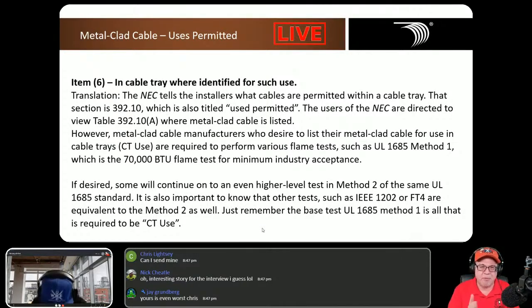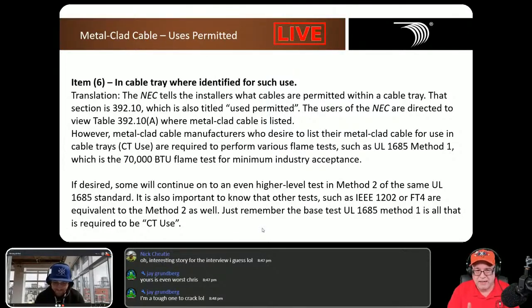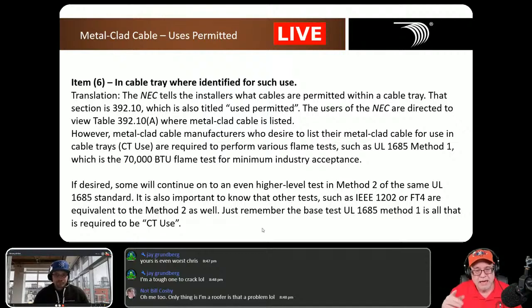Item number 6. This one is saying cable tray where identified for use. This is when you see it marked on the side of your MC. The regular MC that you would see with the armor, whether it's aluminum or steel, because it can be either one, is not going to have any printing on it. So it's going to be on a tag or a label on the coil, or if it's in a barrel, like we sell it in barrel packs, you can get massive amounts of wire length on these barrels. The standard allows me to mark it on the side of the barrel. If it is rated for use in a cable tray, which means it passed the minimum UL 1685 Method 1 test that we talked about earlier, then you'll see CT use or cable tray use on there. If you see that marked, then you know it met the minimum required standard to go inside of a cable tray. And it has to be marked as such.